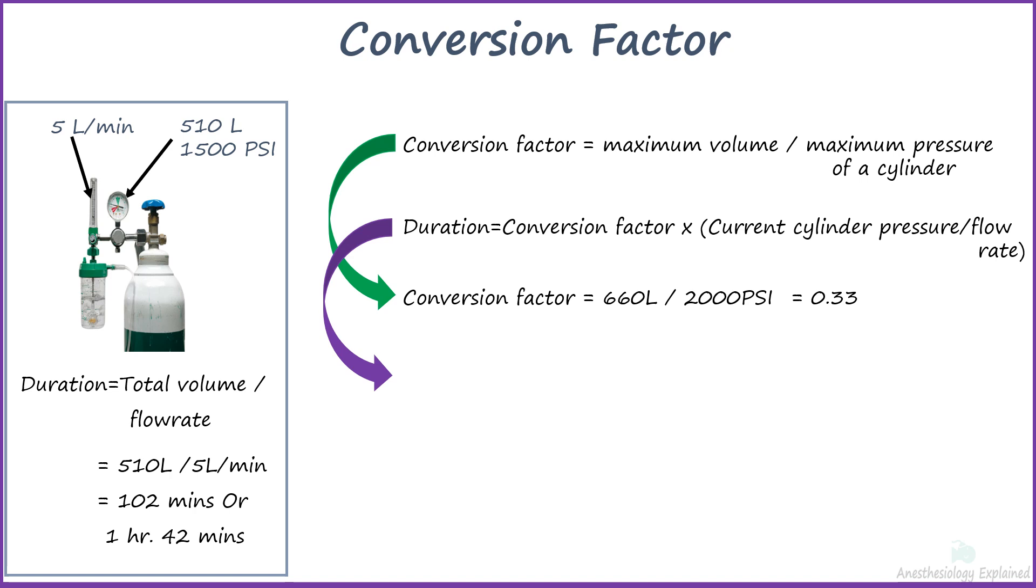Let's take the same example from the previous slide. Using cylinder gauge pressure as 1500 psi and the flow rate as 5 liters per minute, we get 0.33 times 1500 divided by 5, which equals 99 minutes or 1 hour and 39 minutes, which is the same time. But it is advised to use the conversion factors the manufacturers provide.